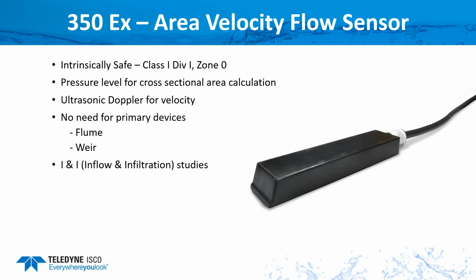You're going to find the area velocity sensors are commonly used for inflow and infiltration studies, for temporary measurement. And the sensors are great for reliability and repeatability. So you may find that if you need redundancy, you can mount two sensors in the same channel. They won't be affected. One little thing that a lot of people don't know about the area velocity sensor, we build ours with a temperature sensor built into it. I bring that up because if you do have infiltration and you see your levels and your flows are going up, but your temperature is dropping, well, you know that you have rain infiltration. That's the root cause or the source of the problem why you're getting more flow.